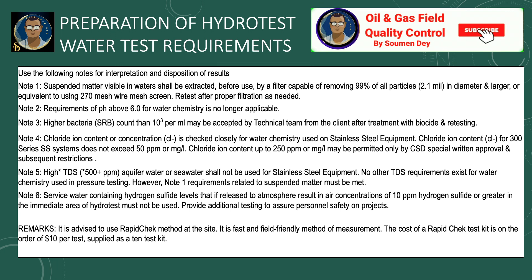Note 4: Chloride ion content or concentration is checked closely for water chemistry used for stainless steel equipment. Chloride content for 300-series SS systems shall not exceed 50 ppm (mg/L). Chloride ion content up to 250 ppm may be permitted only if the consulting service department or technical team from the client gives written approval. Note 5: High-TDS (500+ ppm) aquifer water or seawater shall not be used for stainless steel equipment. No other TDS requirement exists for water chemistry used in pressure testing; however, the suspended matter or TSS value must be met.